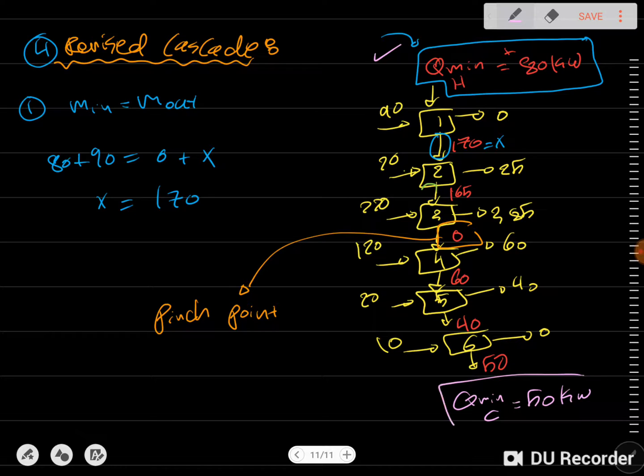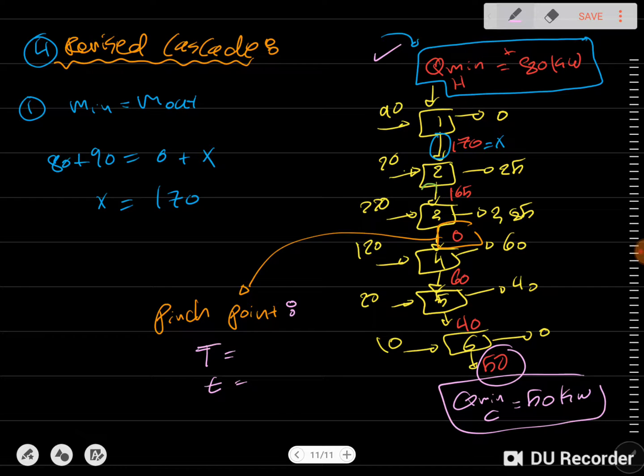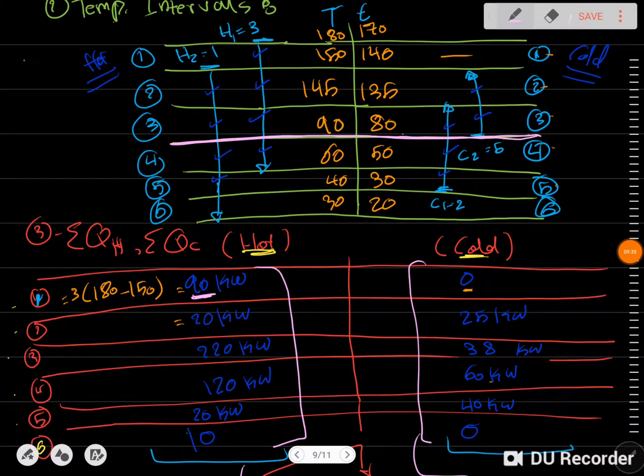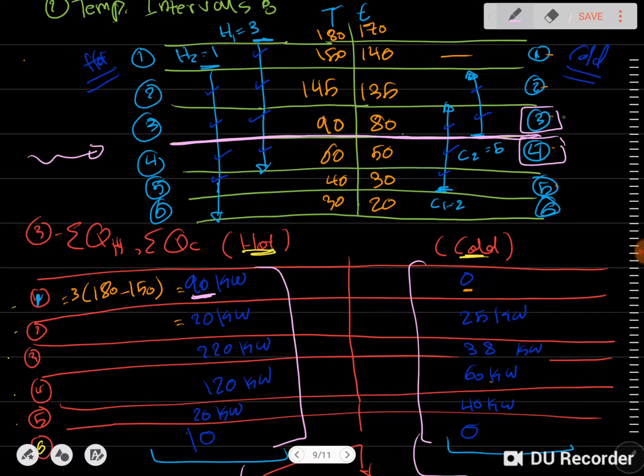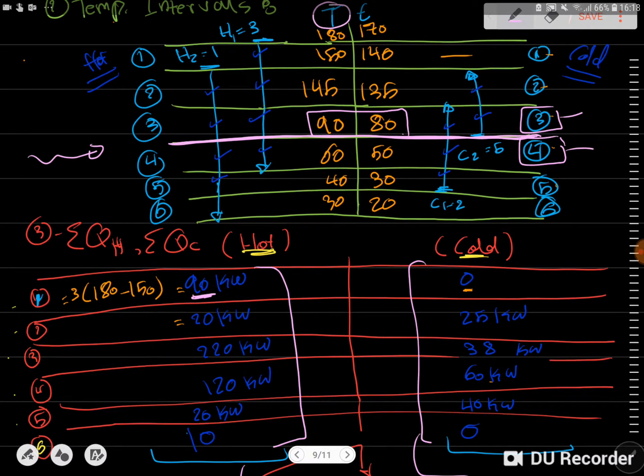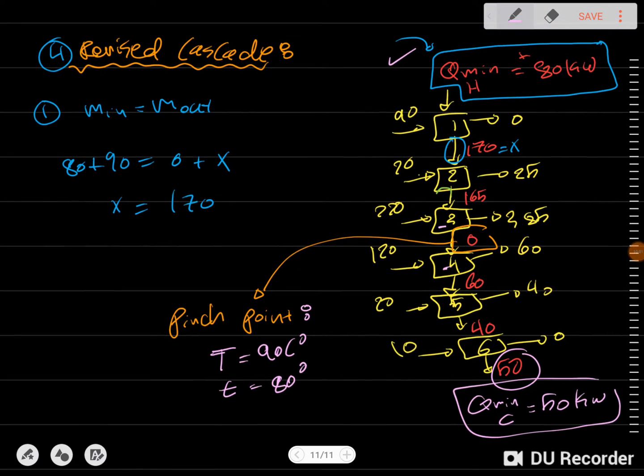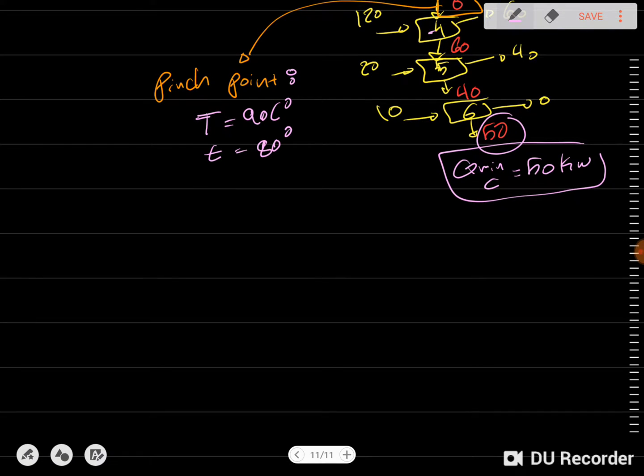By this we know that Q minimum for heating is obtained, and Q minimum for cooling is going to be 50 kilowatts — the last residual value. For the pinch point temperature, we go back to the temperature intervals diagram. The cascade told us the pinch is between intervals three and four, corresponding to the line at 90°C on the hot scale and 80°C on the cold scale.